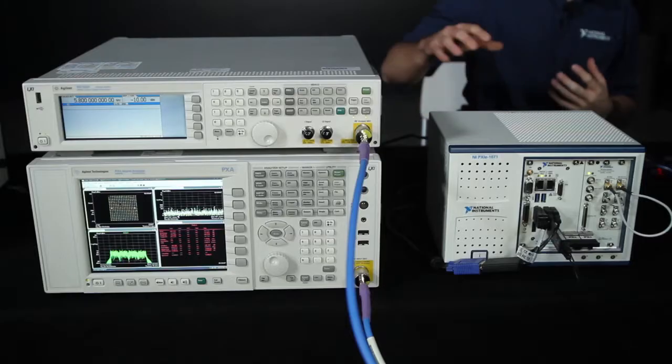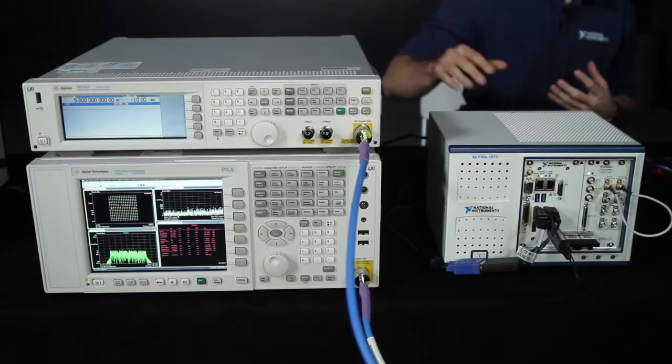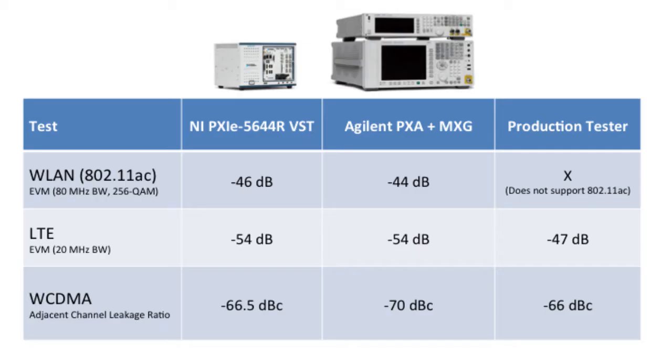We compared the PXIE5644R Vector Signal Transceiver with the Agilent PXA and MXG for other standards as well. Here are our results. As you can see, the PXIE5644R VST is on par with the measurements made by the Agilent PXA and MXG.